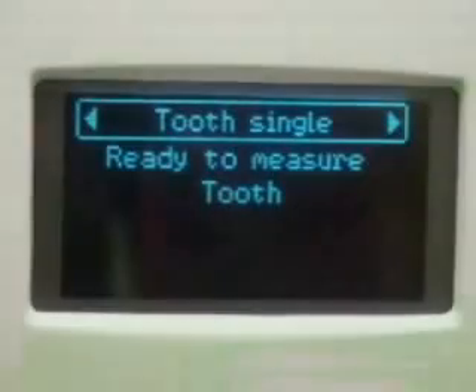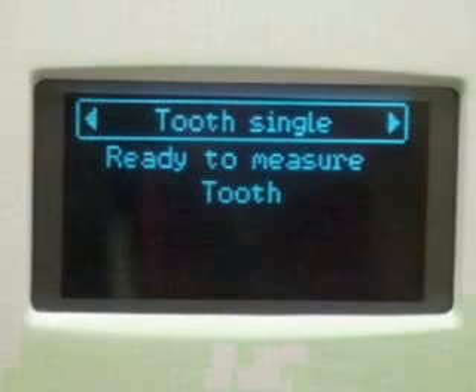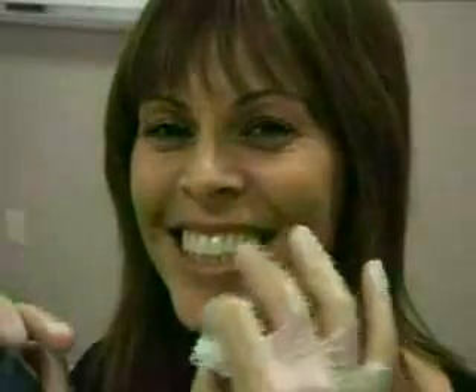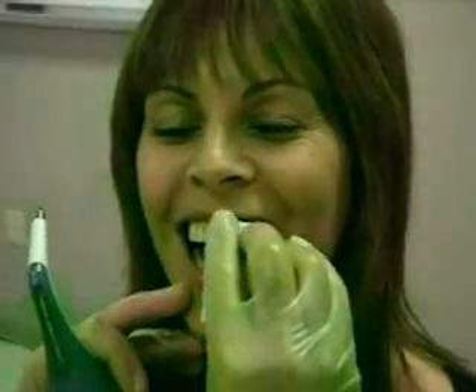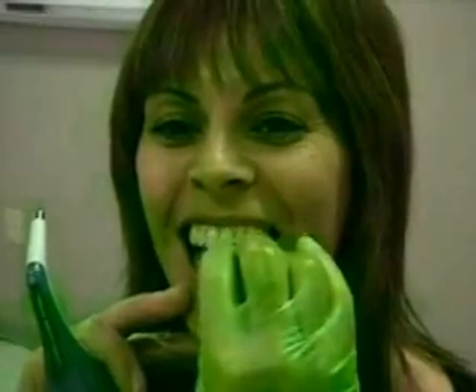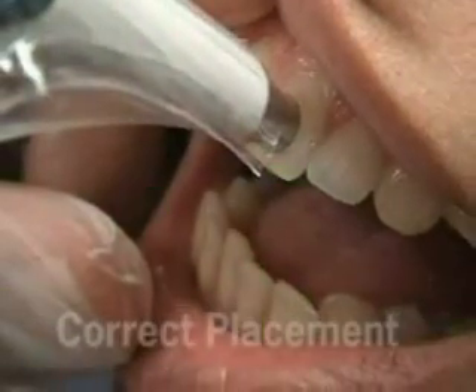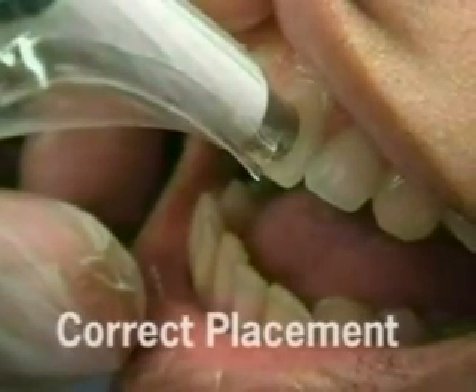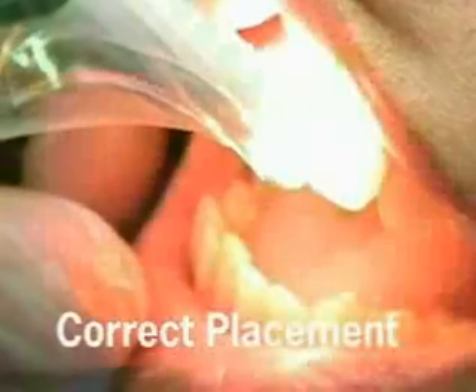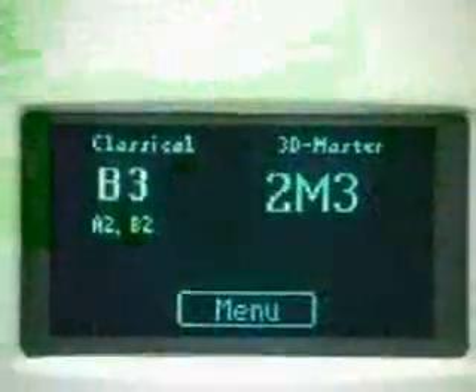Easy Shade may be used to measure a single tooth area on a tooth, referred to as tooth single. It is recommended to clean and remove any stains from the surface of the tooth prior to measurement. It may be necessary to wipe the tooth with gauze to prevent the tip from sliding. While holding the probe tip steady against the tooth, press the measurement button on the handpiece until Easy Shade beeps.